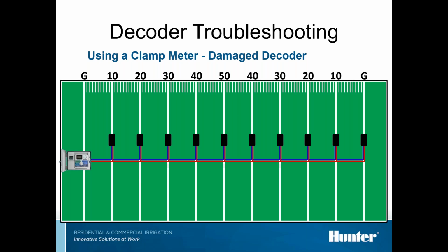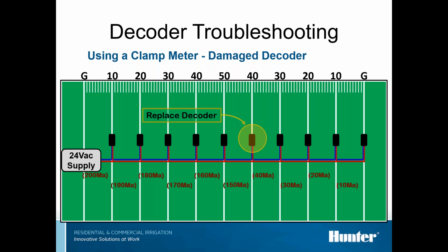A damaged decoder does the same thing. You can have a damaged decoder and it not be extremely high milliamp, but it could still be high. So if you look, you've got 200, 190, 180, 170, and it drops down until you get from 150 and then 40. If you know you have 4 of them past that point, you're at 40, and you went from 150 to 40, there's your damaged decoder. So that's another one to replace.